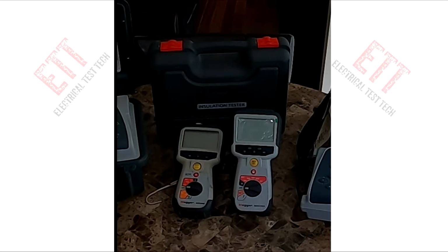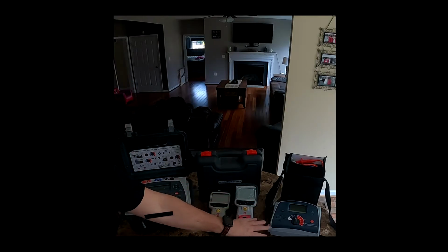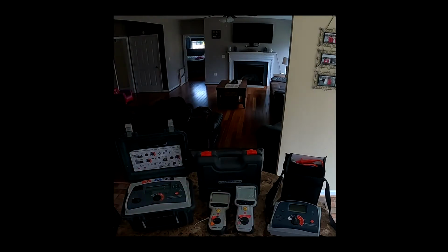A lot of the stuff in our area is 480 volt, 3-phase, 208 volt, 3-phase. Sometimes you come across 240 volt, 2-phase. That's typically residential, and 120. The other two insulation testers here are both 5,000 volt testers. There's a major difference in size between the two of them, but they do the same thing. They apply 5,000 volts DC, and you have a couple different steps between them to do reduced voltage tests.